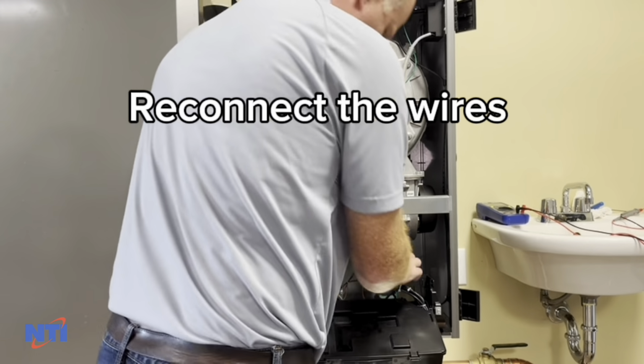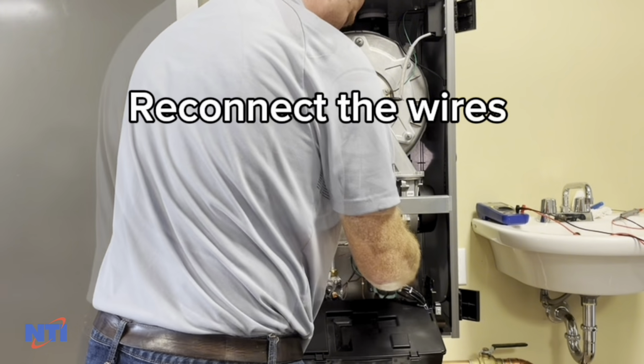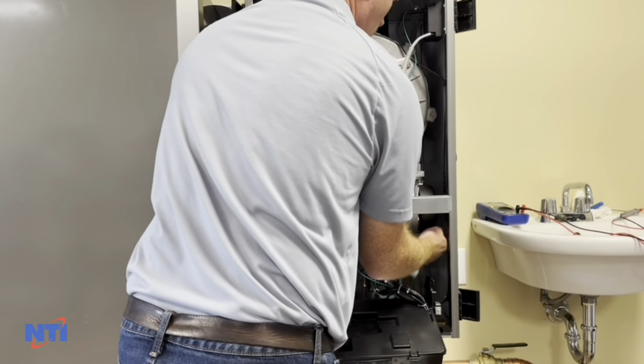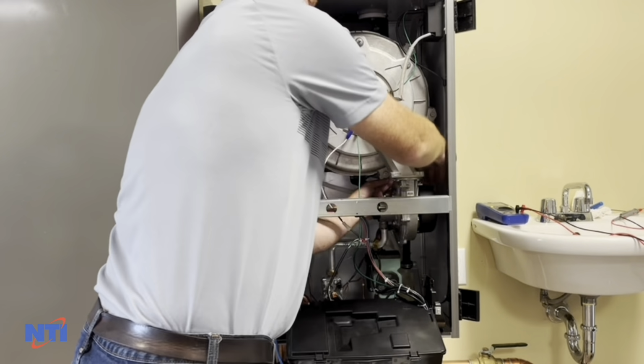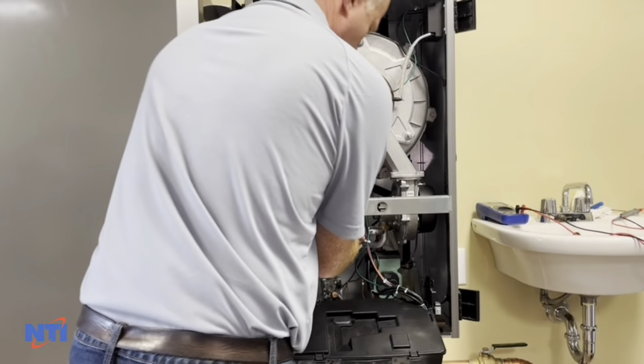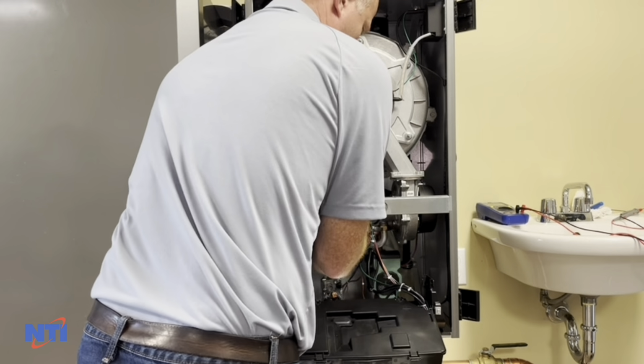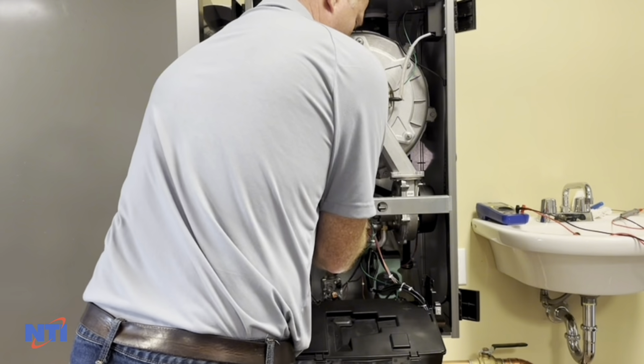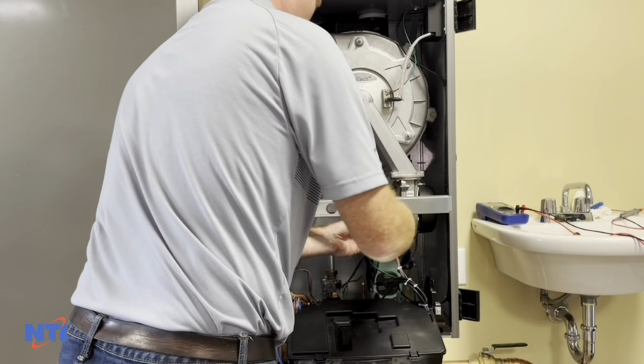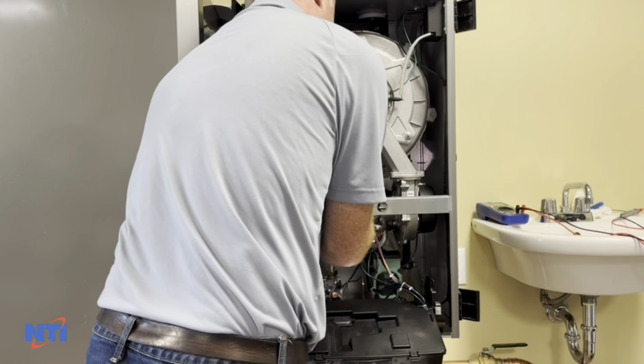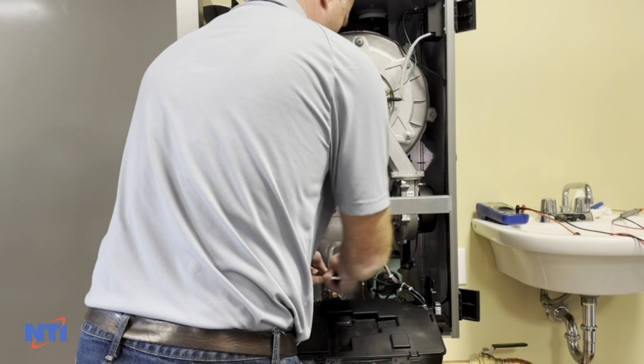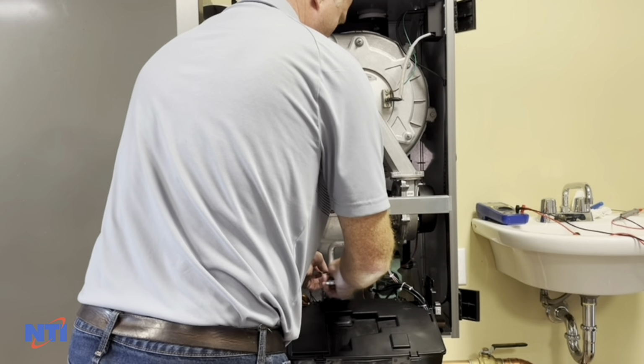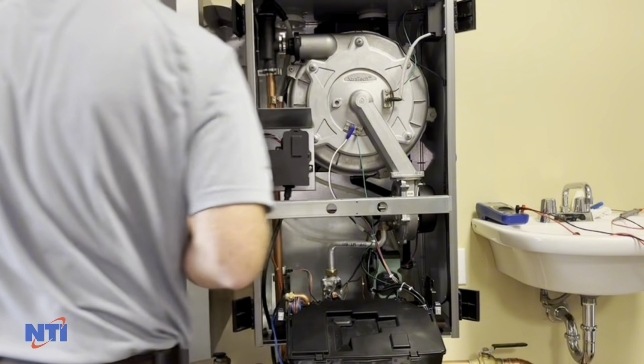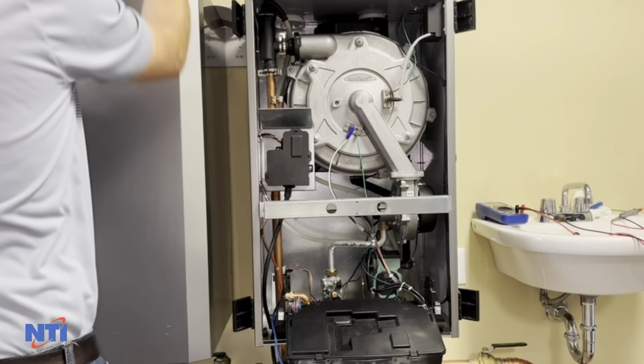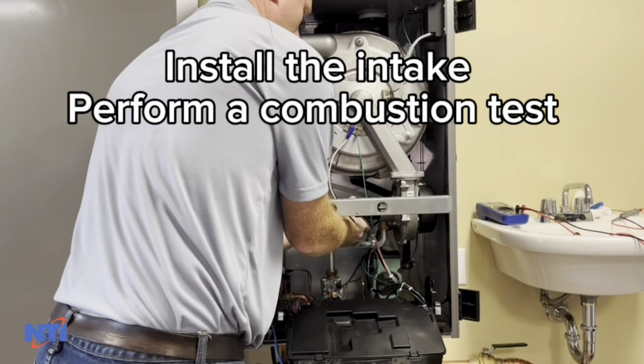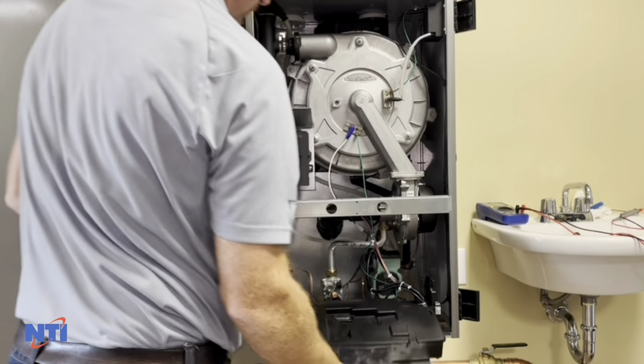Reconnect all of the wires. Reinstall the gas line O-ring, then tighten the gas line at both the gas valve and the Venturi connection. Reinstall the air intake silencer, then perform a combustion test at high and at low fire.